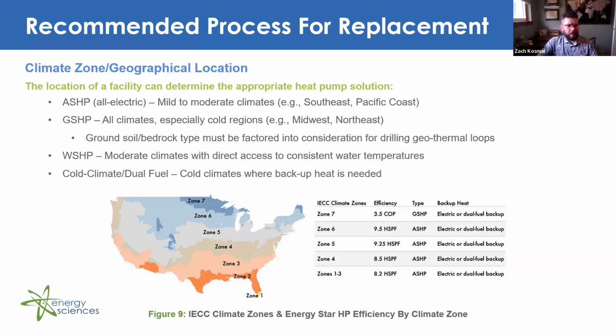For those ground source heat pumps, the thermal conductivity of the ground is dependent on the soil type and moisture content. So with that said, a dry, sandy, rocky soil will have a lower thermal conductivity, or rather lower rate of heat transfer. So the presence of bedrock may impact the type of geothermal loop that can be installed. If you have shallow bedrock that's maybe less than 5 feet from the surface, that can make it almost impossible to install a horizontal loop installation.